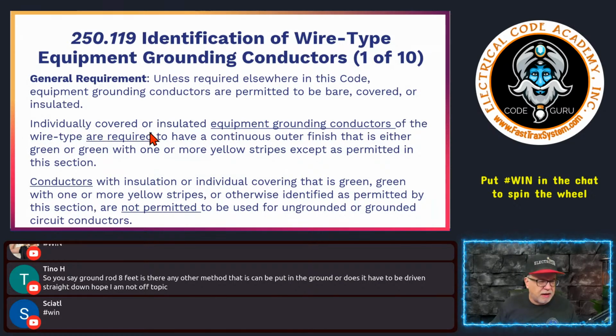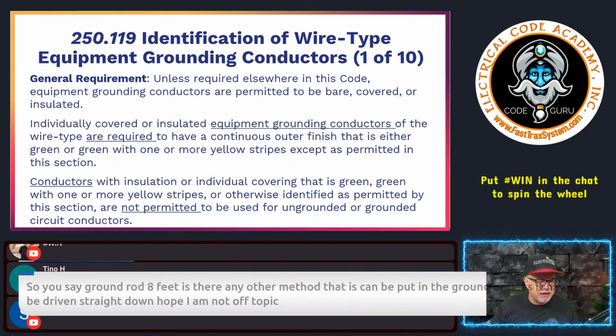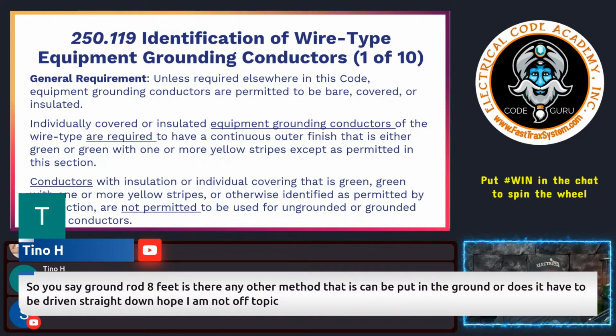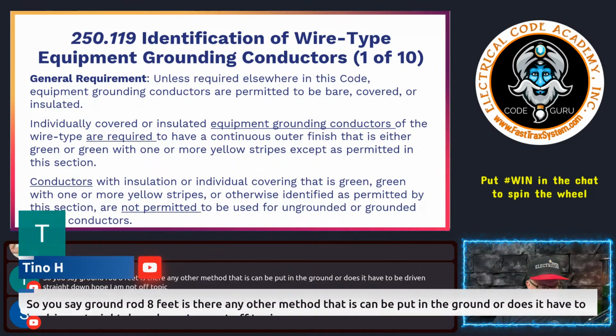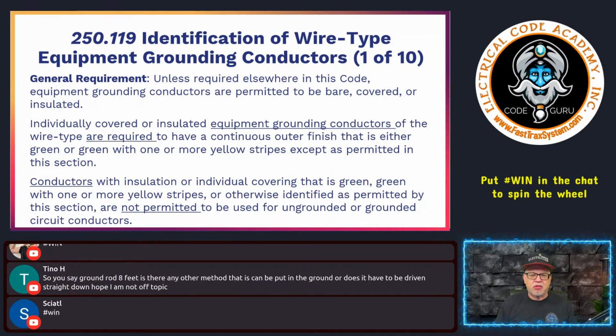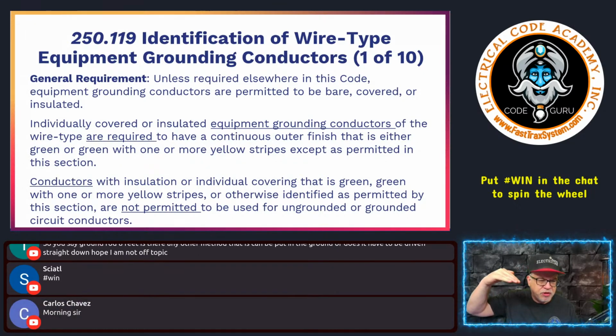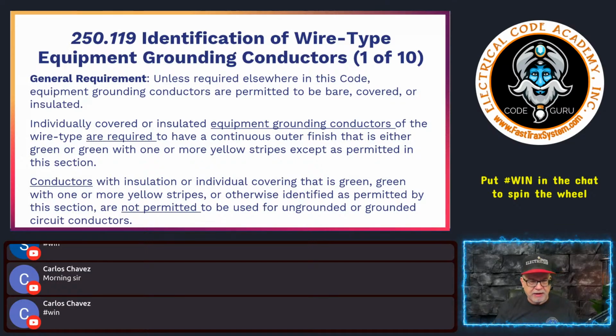Tino has a question. That's obviously not about equipment grounds, but we'll read it anyway. Tina says, so you say rods 8 feet. Is there any method that you can put in the ground, or does it have to be straight down? You're a little off topic. The code says that you drive it 8 feet. If you drive it and you hit rock bottom, then it allows you to install it at an angle up to 45 degrees. If you still hit rock bottom, then the code is going to allow you to put it horizontally, but you'll have to bury it, okay?